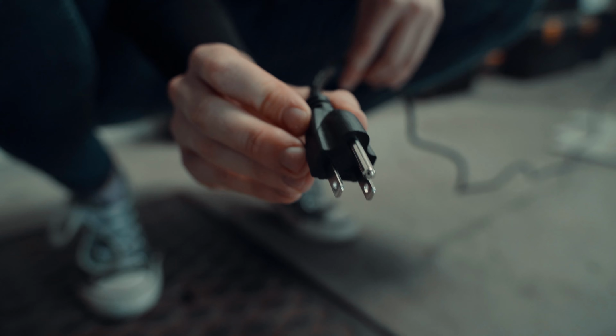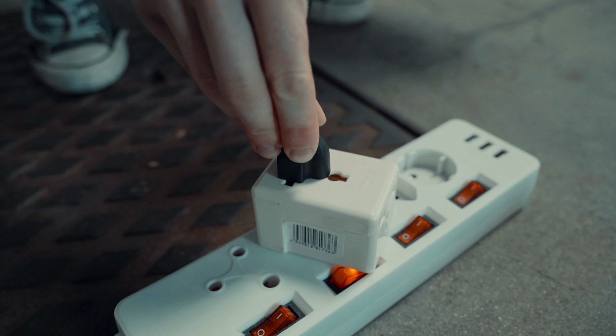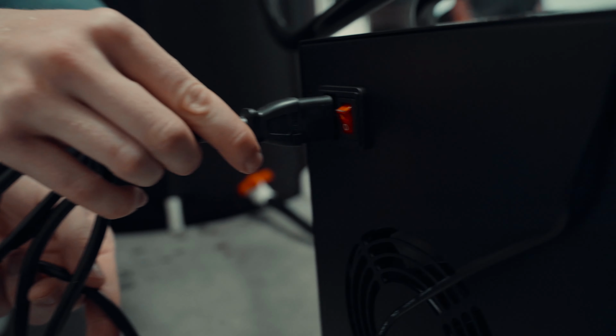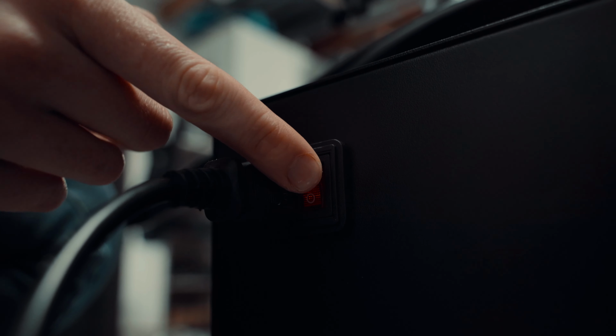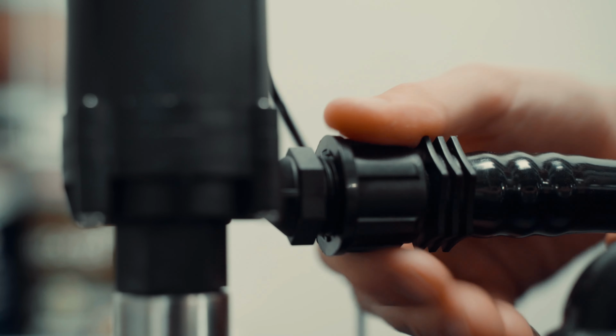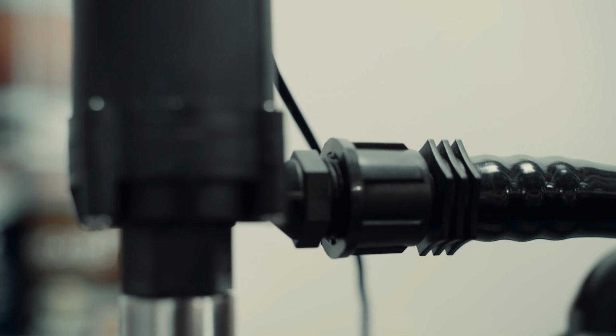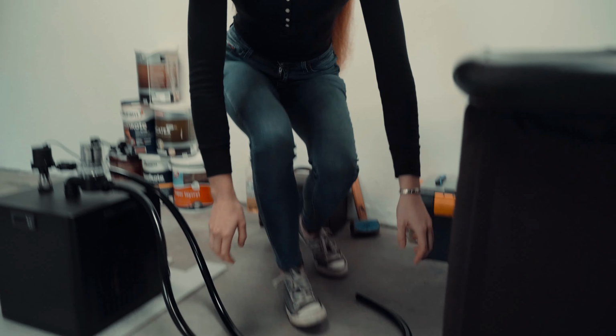Step 8. Power the chiller on. Connect the chiller's main power supply cord to a 110-volt GFCI outlet. Turn on the chiller using the red switch. Please note the chiller and pump will now turn on and water will start flowing. Leave the outlet hose connected to the water pump out on the floor, or in a bucket until water comes out to make sure all the air is out of the system. Once water's running out consistently, place the hose in the ice pod, as water will now circulate.